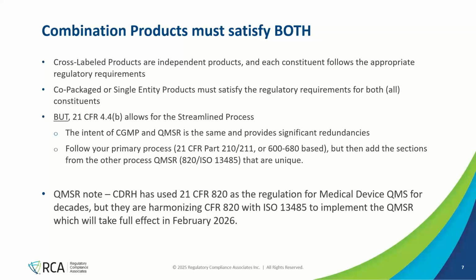So one thing I want to note here is that the FDA has recently, earlier this year, harmonized the CFR to ISO 13485, which is the ISO standard for quality management systems for medical devices. This means that what used to be a little blurb paragraph of regulation in the CFR that described what you needed to comply with has now expanded into an entire section of an ISO standard. This is going into effect in February of next year, so there's no reason to talk about just the CFR anymore, because really everything is going to 13485, and they are referring to this as QMSR instead of just QSR.